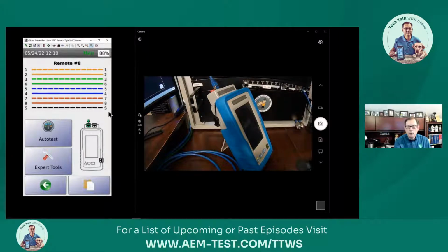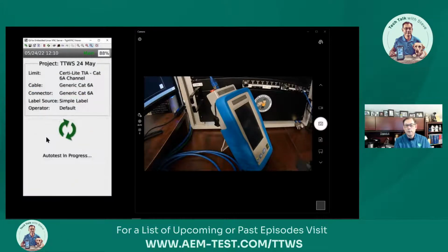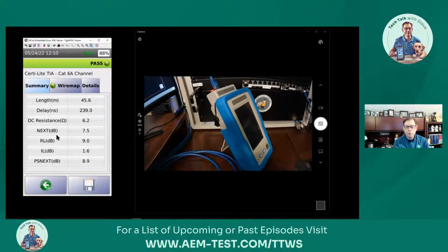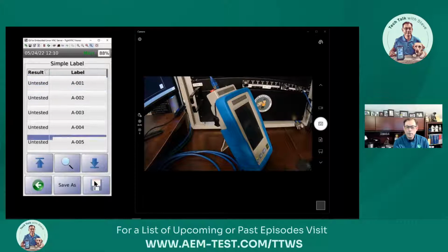Now we're on remote ID number 8, and I'm using multiple remotes here. We have remotes numbered 1 through 8. We'll run another auto test, and hopefully this is a good cable. If I've done my job right, it'll show up as a pass. We can save our test results. This is the physical cable test port, and it did pass. I'll click save, and go up to number 5 to save an A005 out of my list.